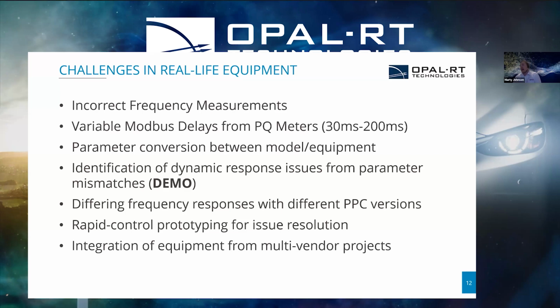One advantage of the hardware-in-the-loop setup is that we can do rapid prototyping to fix these kinds of issues, which of course you can't do on site because we need to go through and provide reports. We can't use the network as a test bed, so we need to make sure the implementation we're going to do will work. In the hardware-in-the-loop environment, we're not dealing with high powers, so it's much easier to do this kind of testing.